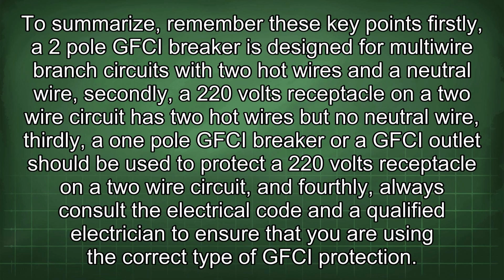To summarize, remember these key points. Firstly, a 2-pole GFCI breaker is designed for multi-wire branch circuits with 2 hot wires and a neutral wire. Secondly, a 220 volts receptacle on a 2-wire circuit has 2 hot wires but no neutral wire. Thirdly, a 1-pole GFCI breaker or a GFCI outlet should be used to protect a 220 volts receptacle on a 2-wire circuit. And fourthly, always consult the electrical code and a qualified electrician to ensure that you are using the correct type of GFCI protection.